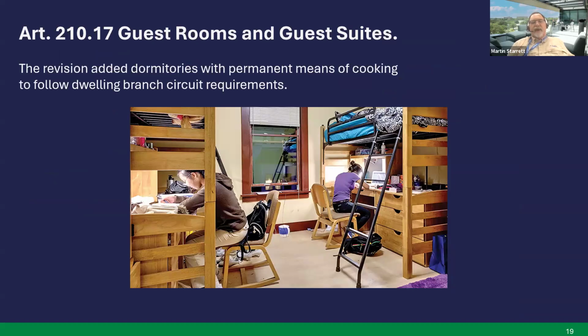Next slide. Article 210.17, guest rooms and guest suites. The revision added dormitories with permanent means of cooking to follow dwelling branch circuit requirements. So if you have a dormitory that has permanent means of cooking, you're going to have to follow those dwelling unit requirements, which include your outlets placed and required branch circuits and that kind of thing, similar to what we do right now in hotels and motels. Next slide.